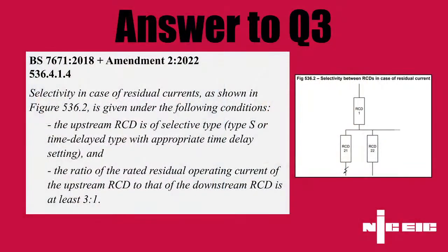And the ratio of the upstream RCD to the downstream RCD should be at least 3 to 1. So if you have a 30 milliamp RCD protecting your outgoing circuits, then upstream of that you're going to be looking at 3 to 1, so anything above 90, so you'd be looking at 100 milliamp in that regard.